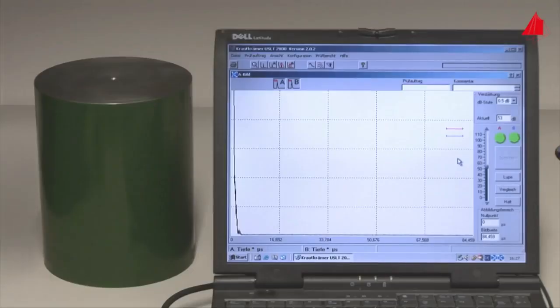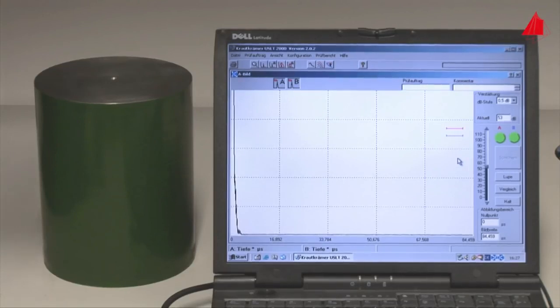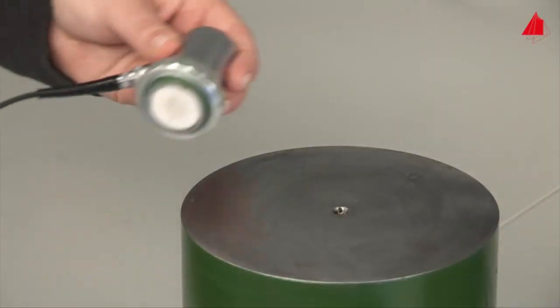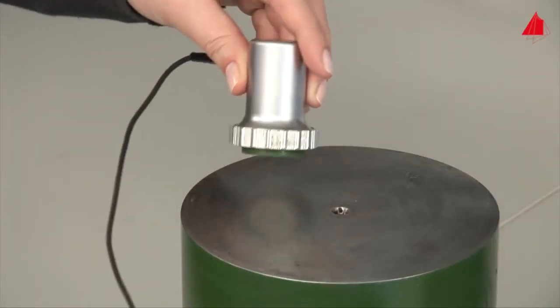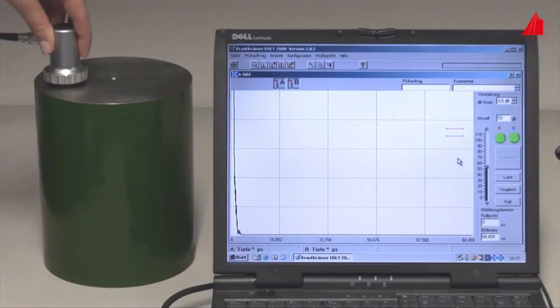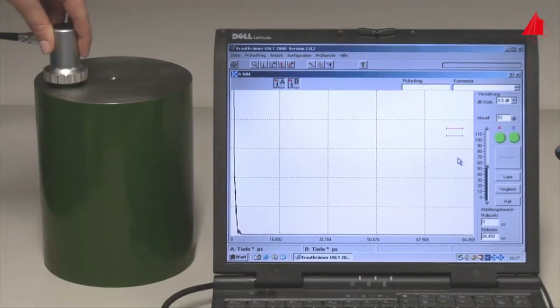A computer operates the probe via a plug-in card and power electronics. On the monitor, the intensity is plotted upwards and the time is plotted to the right. After placing the probe on top of the cylinder, initially no echo at all may be seen on the monitor. The reason for this is the too small contact area between the probe and the workpiece.